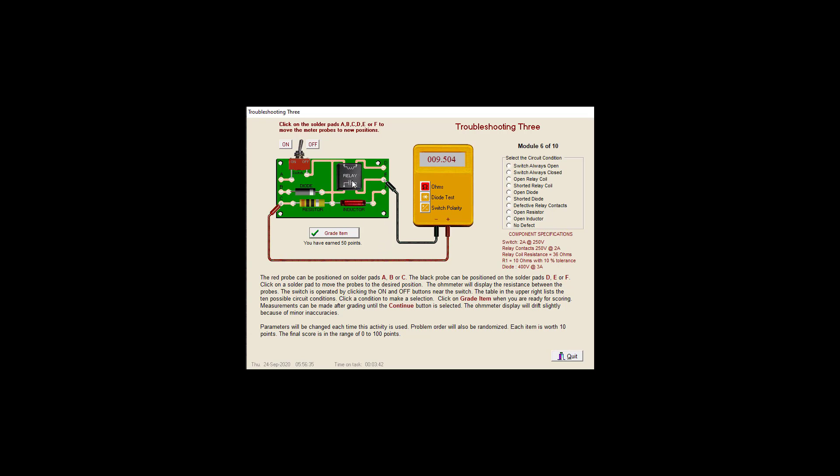That means our contact is shorted. We shouldn't get any continuity. That's an open contact. We've got a shorted defective relay contact.